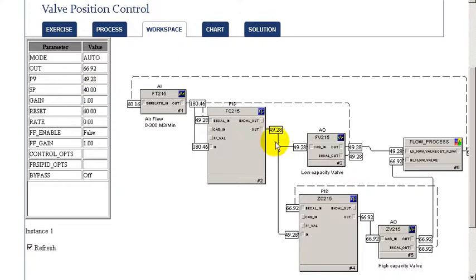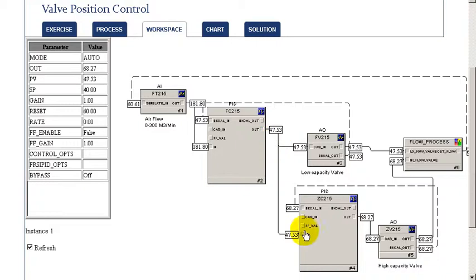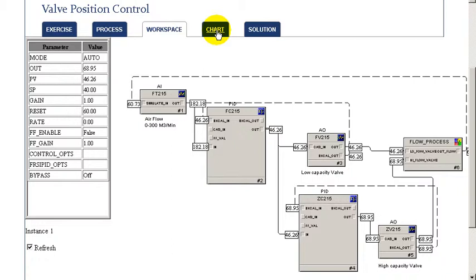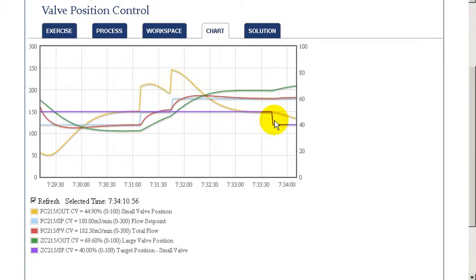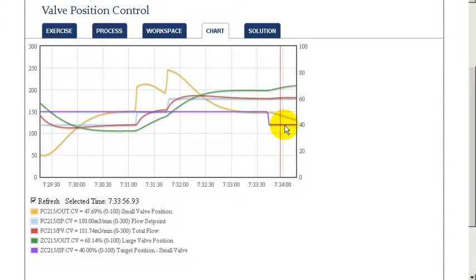As we can see, having changed that valve position target, this bigger valve starts to move. This causes an error in our flow and so our smaller valve also starts to change to correct for that. And as a consequence, our smaller valve goes to the new target position long term.